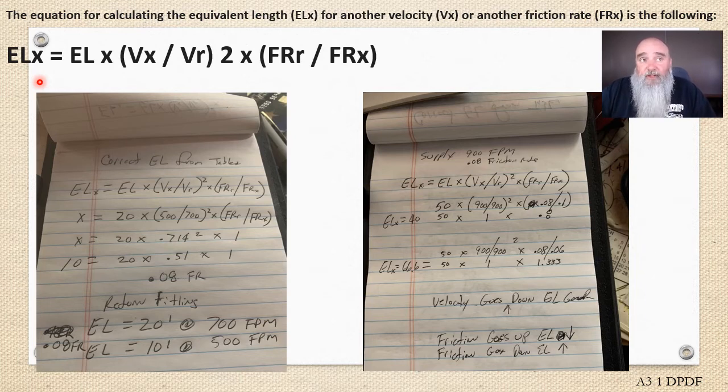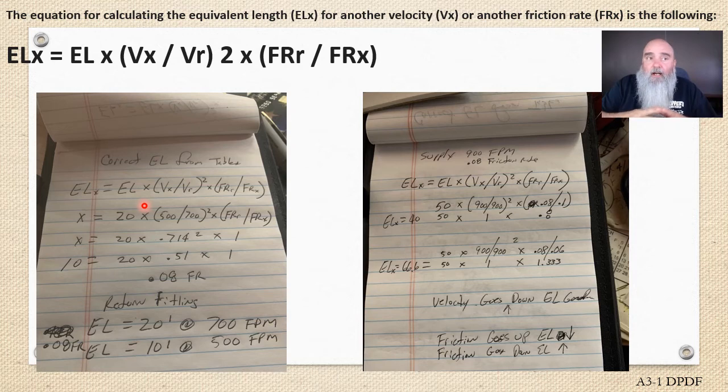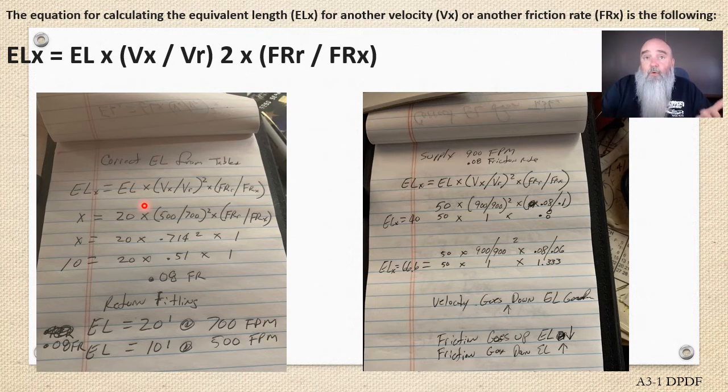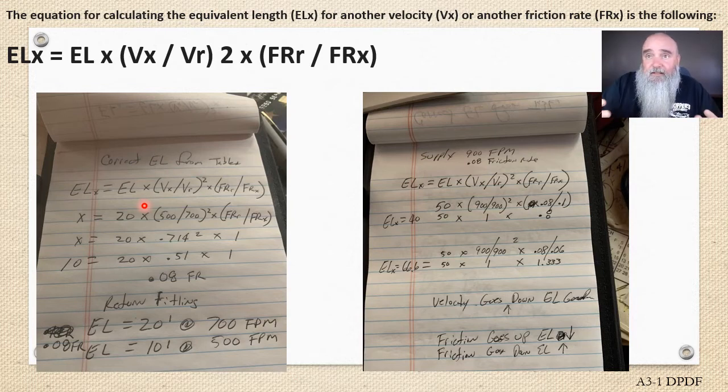And I think what you'll find is that when you adjust your velocity, and the most common thing we do on purpose—I would like to think—is run our air through our trunks at a lower velocity, which will allow us to enjoy a lower pressure drop or a lower EL. That can make it so we can use slightly smaller ductwork and we're still following the guidance of Manual D.